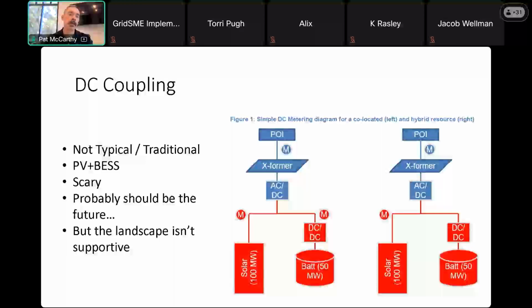So DC coupling, just a quick tangent. Basically, it allows two fuel types to share a lot more infrastructure than an AC coupled arrangement, and it lets you capture basically free energy. You've got the medium voltage transformer at each inverter pad that's now shared between twice as much market transaction. You've got all the medium voltage cabling from your array into your substation, all the substation protection control, the inverters themselves - all of this is now shared. So you're getting a lot more bang for your buck in terms of infrastructure and the resources you can put behind it. You have less capital and less O&M cost to build the same amount of PV plus BESS in a DC coupled configuration versus an AC coupled configuration.